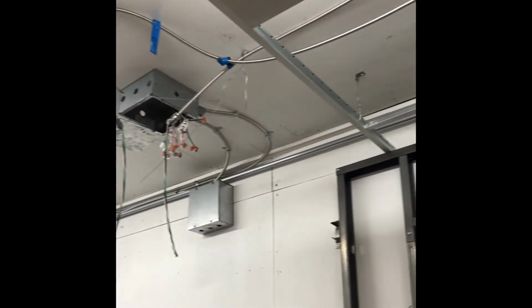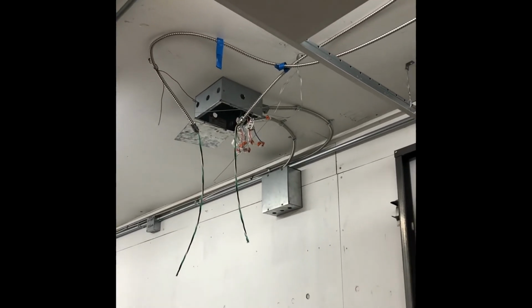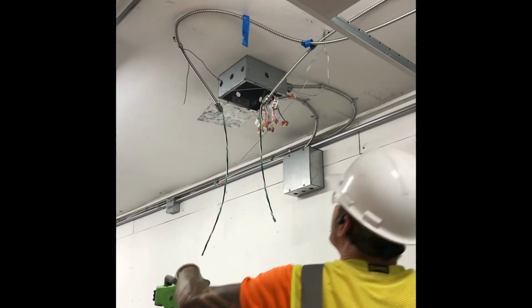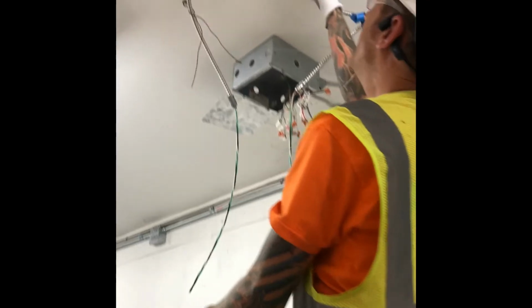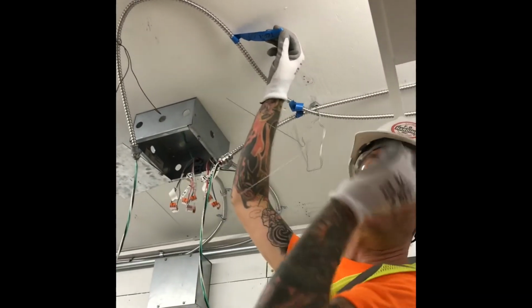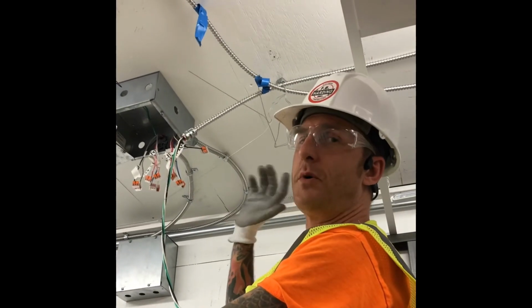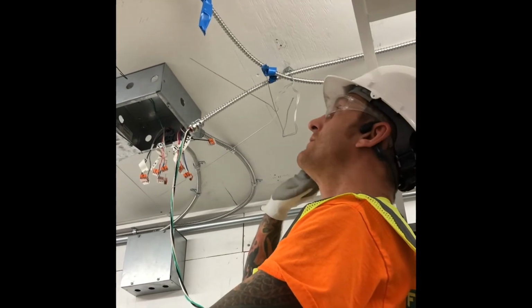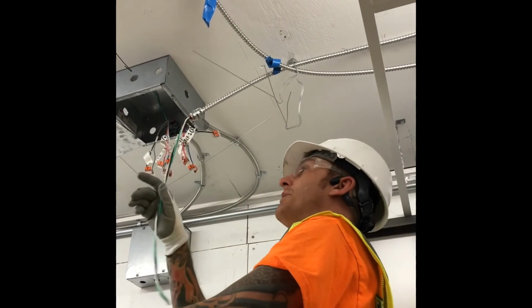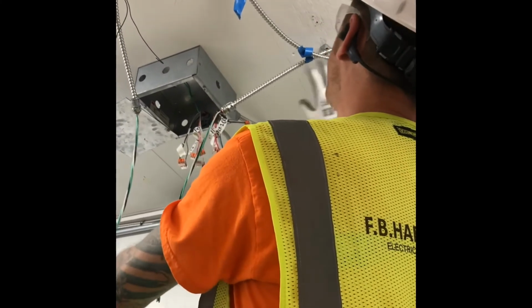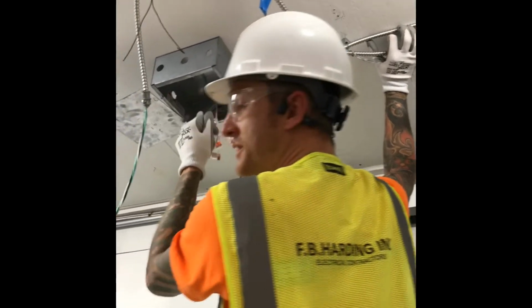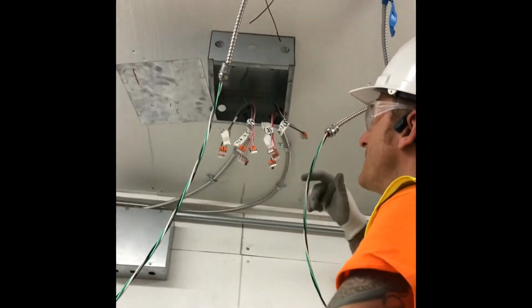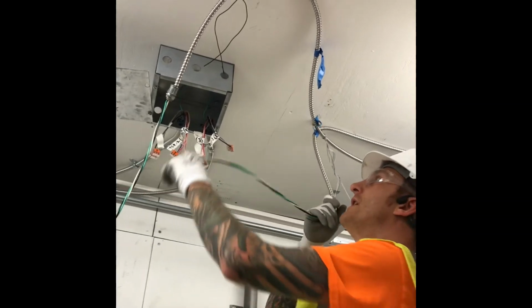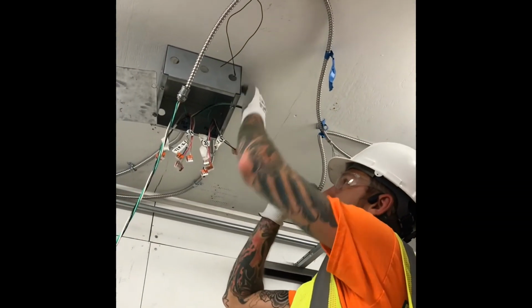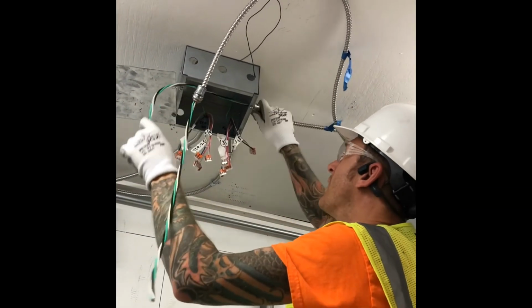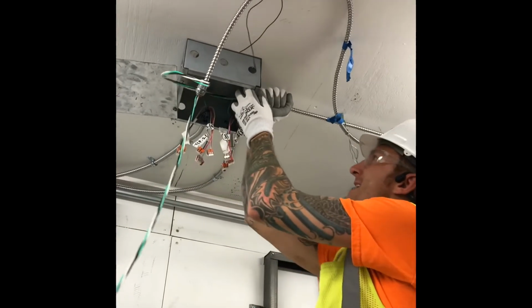Over here is the junction we talked about, where circuit 1 and circuit 3 are, labeled correctly. If these weren't labeled, we'd have to trace it back, and a lot of times the drywall's already up, making it very difficult to trace, with lots of troubleshooting and wasted time. At this point you'd look in the box and test it with your tester to make sure nothing's energized. We'll cover using the tester in the next exercise, but right now we're just working on the cables and how you put them in the box.